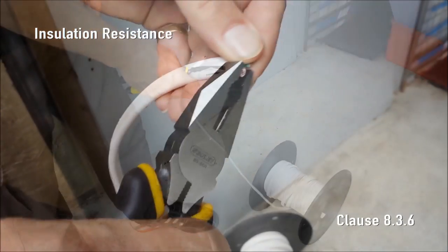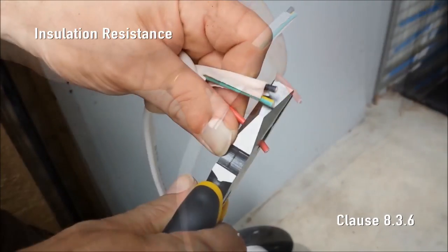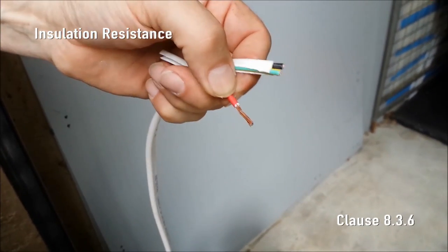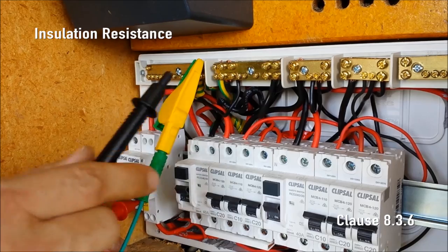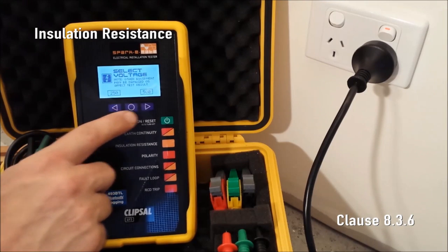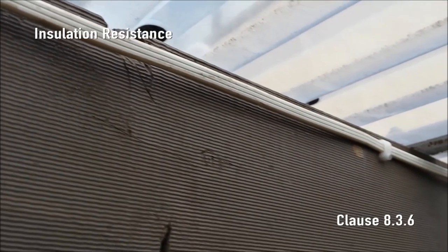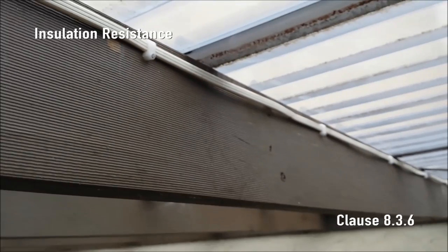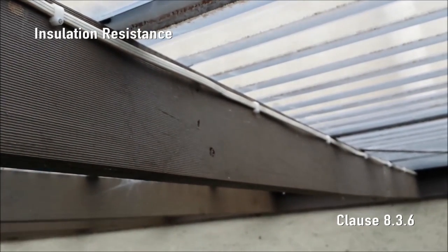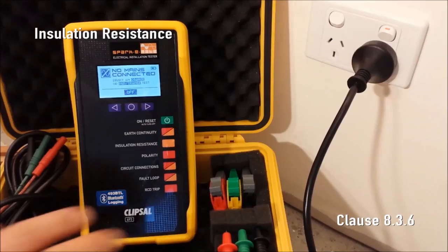Insulation Resistance. Thermoplastic sheathed cabling or TPS cabling must provide very high insulation resistance between live conductors and earth. The insulation resistance of an entire installation can be performed at the switchboard using the 493L test lead set. For today's demonstration, we'll run an insulation resistance test from a final sub-circuit at a socket outlet. SparkyMate tests the integrity of connections in junction boxes and cable insulation from the switchboard to the socket outlet. The insulation is stressed by applying a direct voltage of either 250V or 500V. First, turn off the circuit breaker for the sub-circuit under test, then press the insulation resistance button.